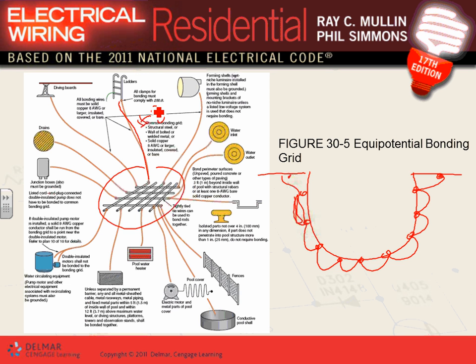You don't have to do a grounding rod or anything like that? No, not grounding rods. You still depend on the grounding rod of the building to ground the system. Grounding rods are there to ground the system. So this would be tied into the... Yes, absolutely. This all will be bonded together, and when you power this, the equipment grounding conductor that comes with the system will be tied to it. Same thing, all this equipment will be powered, and the equipment grounding conductor will be tied to it.